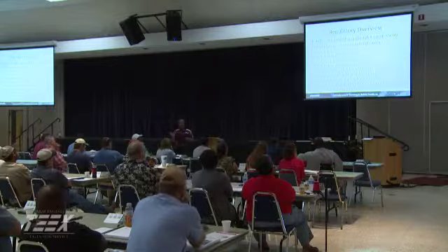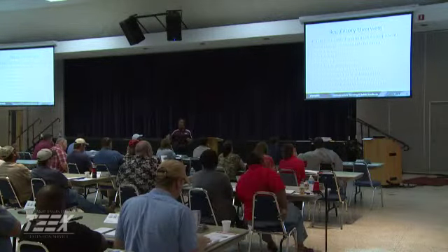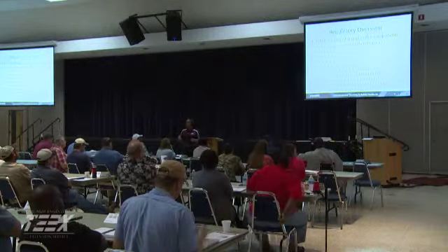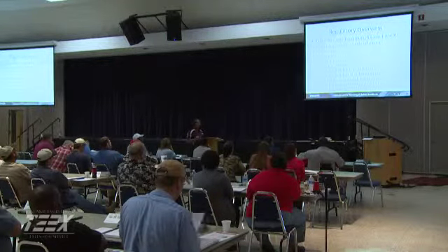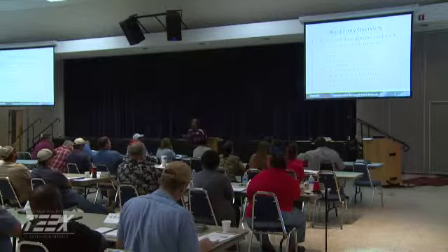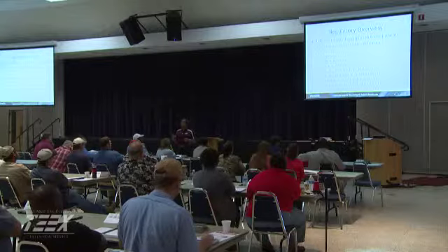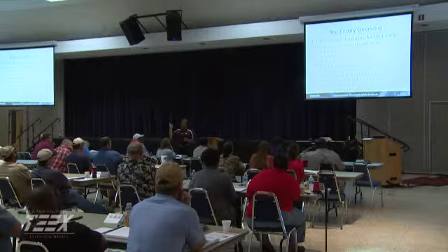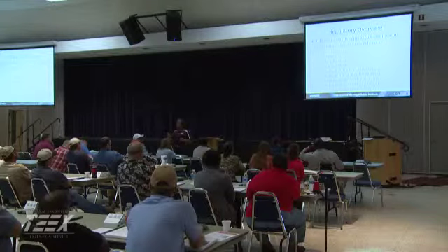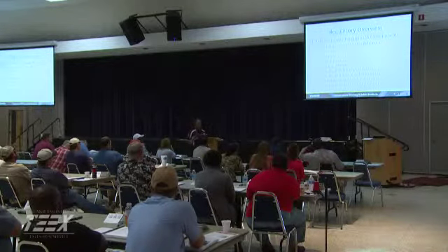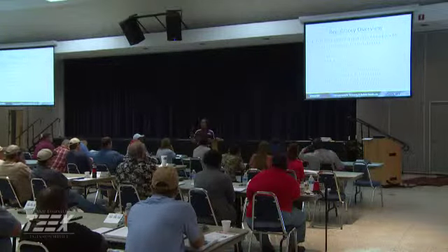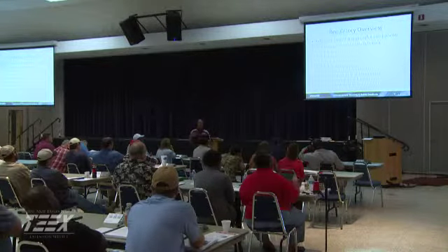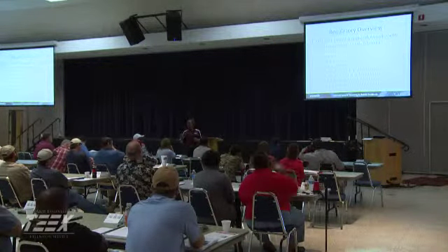With the sanitary surveys, again, we're going to the source. We're looking for possible contamination in and around the source waters where we're pulling from, or our well if that's the source. Then we're going to walk through the treatment schematic. For most groundwater systems, what type of treatment is mandatory? Usually just disinfection, that's it. Some of you all may add some type of polyphosphate if you have an iron problem, or fluoride, but usually not much is done treatment-wise to groundwater unless you have a special case, you have a high mineral content or gas and you have to remove that with aeration or something like that.